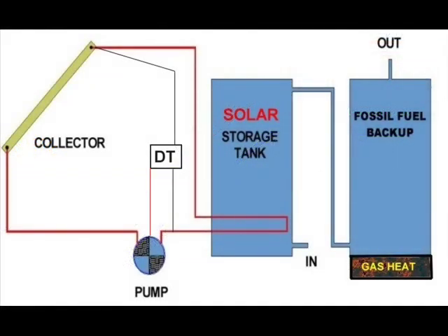Active solar hot water systems use pumps and differential controllers to automate the process of collecting and storing solar heat. So storage tanks may be located in basements far from the area of heat collection. Active systems do consume some power, but the value of heat collected is great compared to the power used to circulate water.